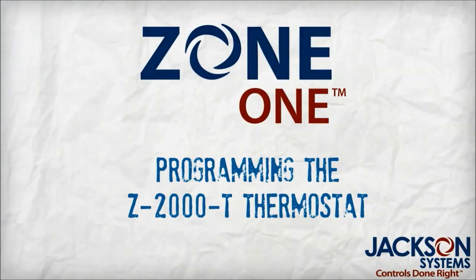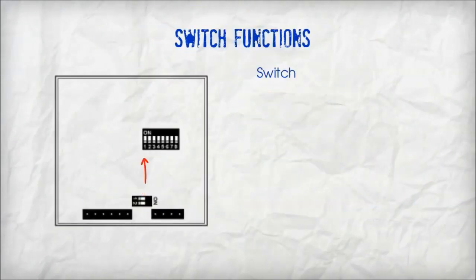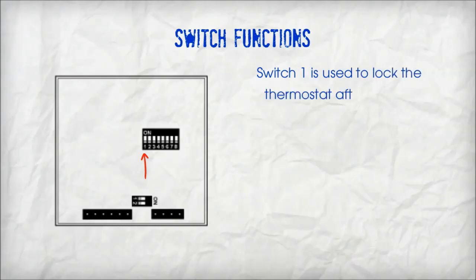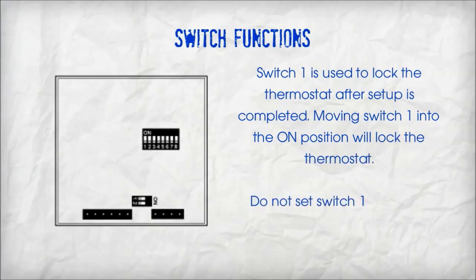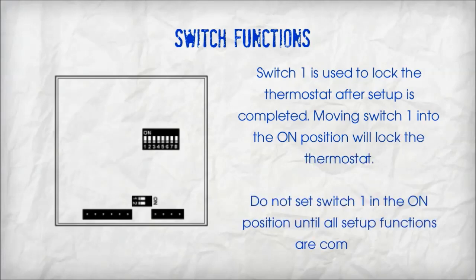Programming the Z-2000-T Thermostat. Switch 1 is used to lock the thermostat after setup is completed. Moving switch 1 into the on position will lock the thermostat. Do not set switch 1 in the on position until all setup functions are complete.